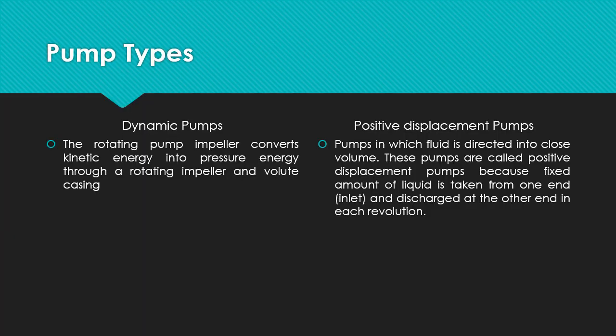What is the major difference between dynamic pumps and positive displacement pumps? In dynamic pumps, the rotating pump impeller converts kinetic energy into pressure energy through a rotating impeller and a volute casing. Whereas in positive displacement pumps, the fluid is directed into a closed volume. These pumps are called positive displacement pumps because a fixed amount of liquid is taken from one end and discharged at the other end in each revolution.